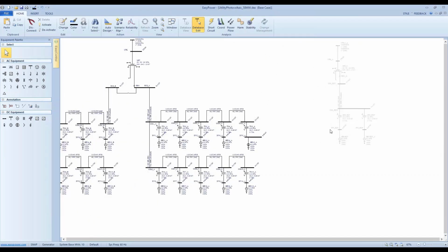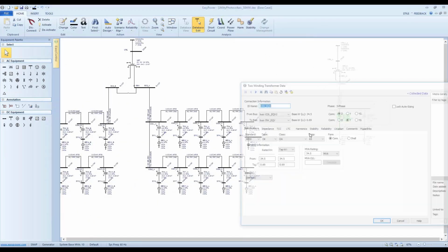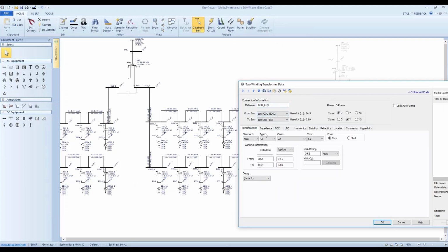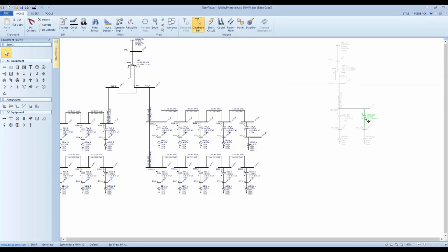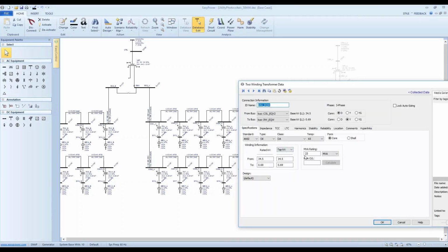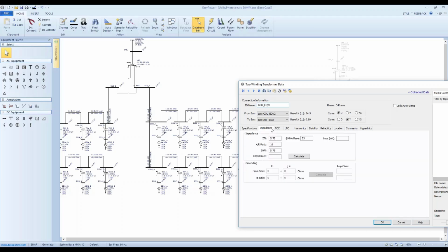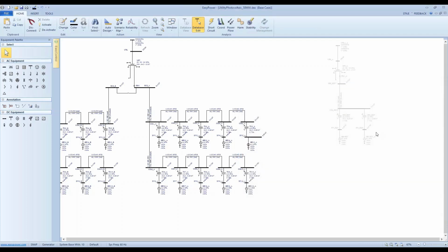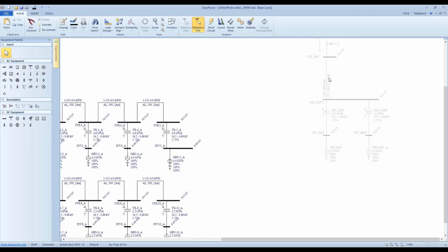Now, GSU is the same. You can see that impedance is the same. I just changed the MVA rating by 10 times for the 2.3 MVA transformer. For the 4.6 MVA transformer, I multiply by 5, get my 23 MVA rating, and the base, I don't change the impedance at all. That should be it. How about the collector system equivalent?